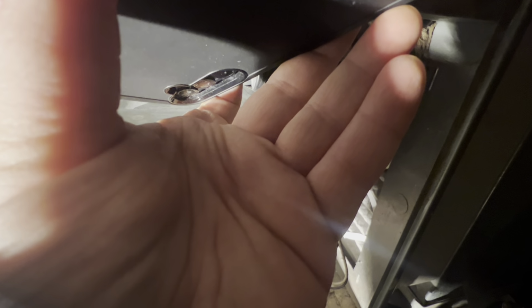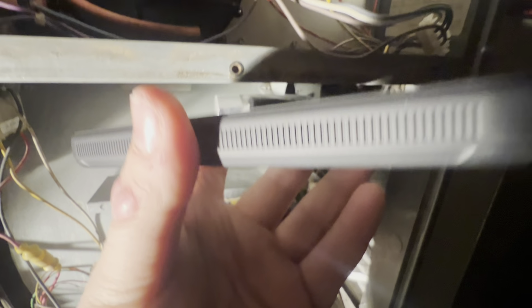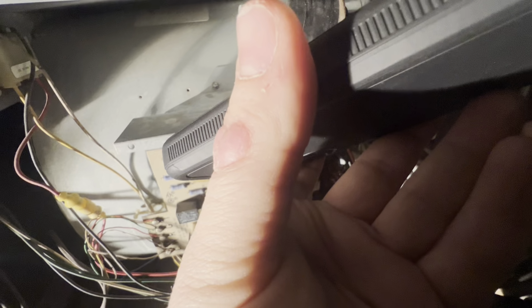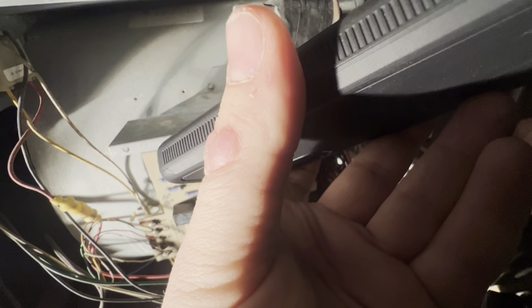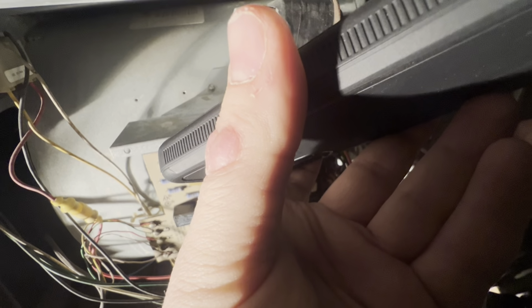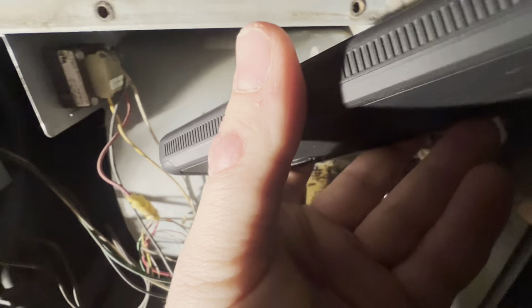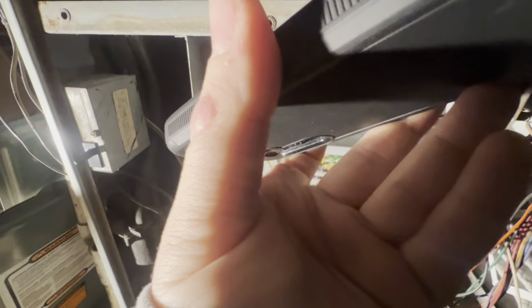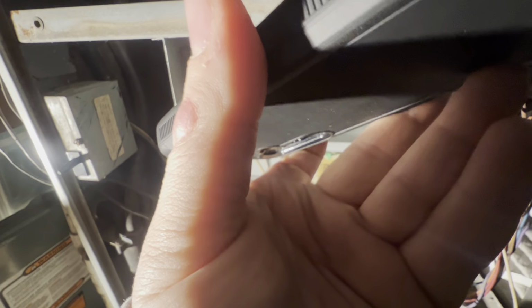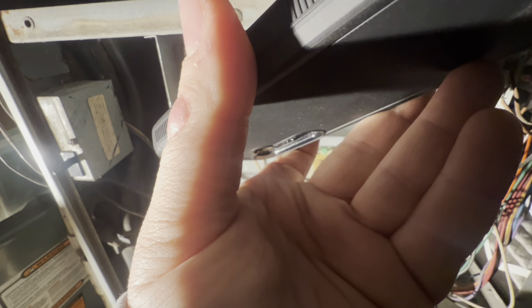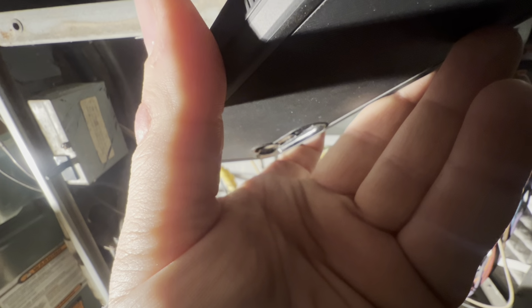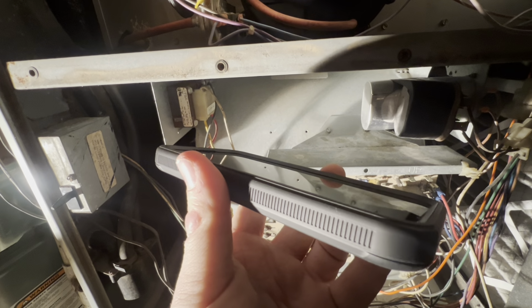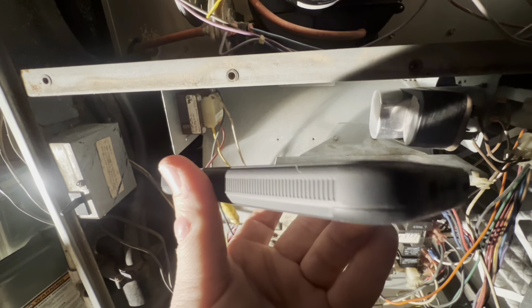All right. Give me just a moment here and put you on hold. Sure. All right. Looks like there's 2 pressure switches on here. Yeah. I believe there's one positive by the drain and one negative attached to the inducer housing. I'm looking for the one that's attached to the inducer housing. Okay, perfect. Looks like I have one here. Oh, that is beautiful.